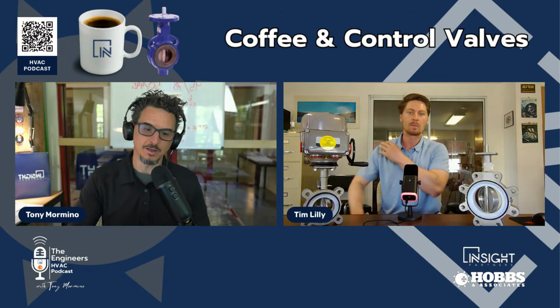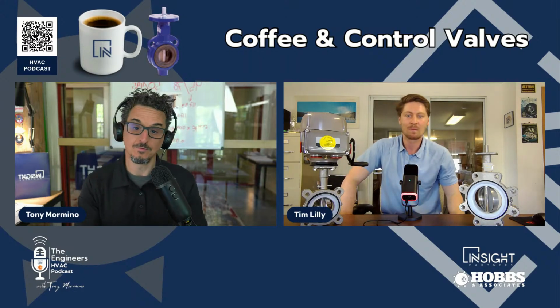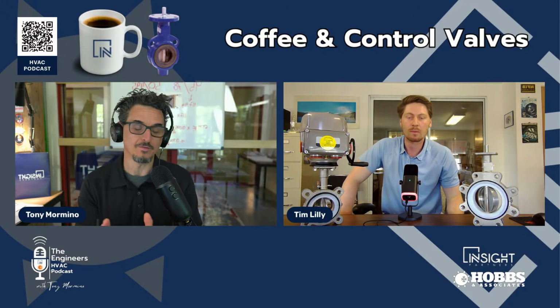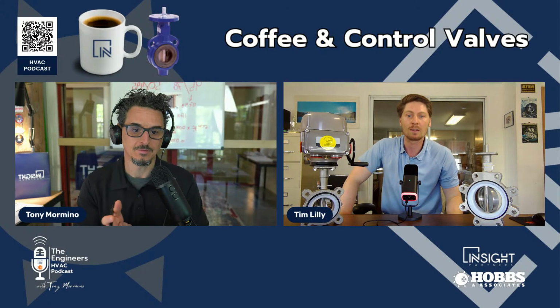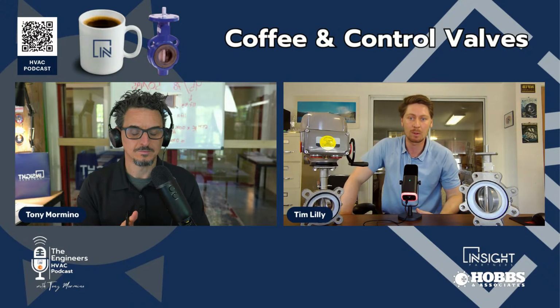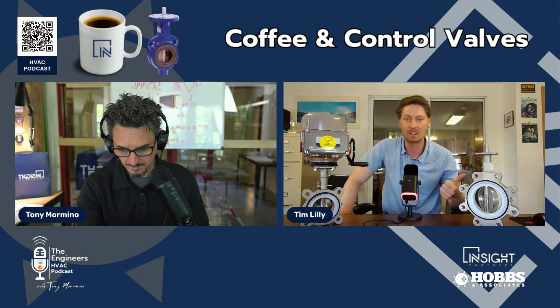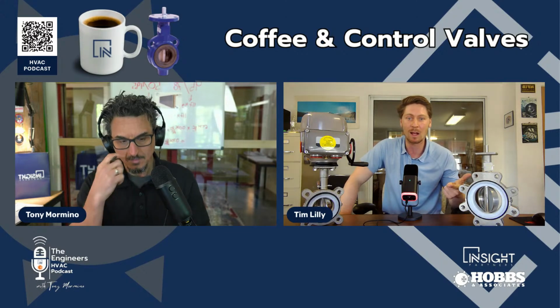So you don't want to crack it open 10% and get 40% of flow, similar to kind of an air valve, like a VAV box. And so it makes your modeling very predictable. But the problem is, if you want those kind of flow characteristics, you have to go with a globe valve or a characterized ball valve, which are A, very expensive, and B, take up a lot of space.